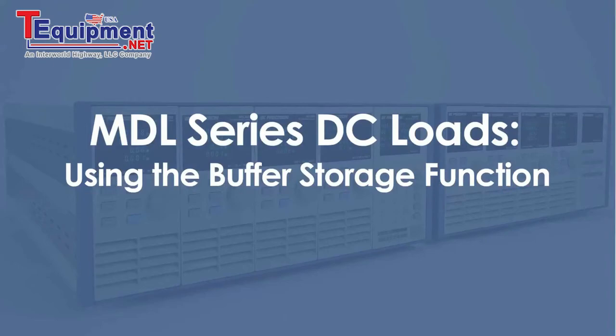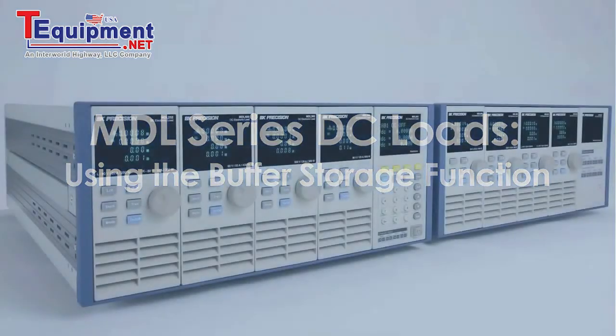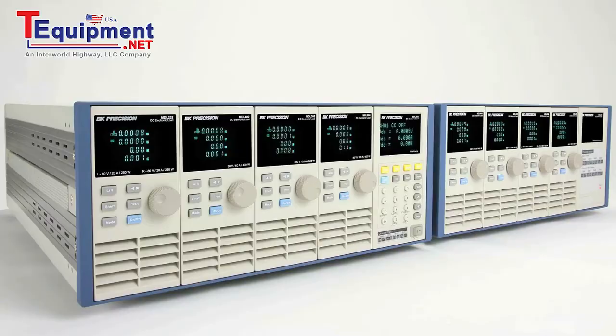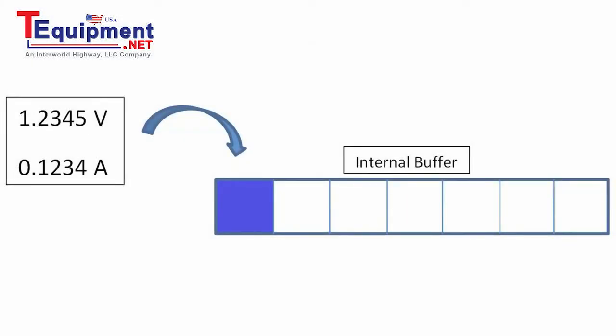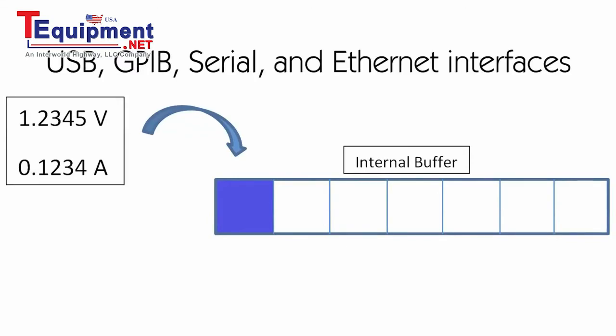I'm going to show you how to use the buffer storage function available on the MDL series DC electronic load. Buffer storage operation allows the user to store measured voltage and current readings temporarily into internal buffer memory, which can be retrieved with remote commands to a computer. The main advantage of this operation is speed, because all measurements are directly stored into the internal buffer without any additional post-processing time, which is existent when querying measurement data using USB, GPIB, serial and Ethernet interfaces.